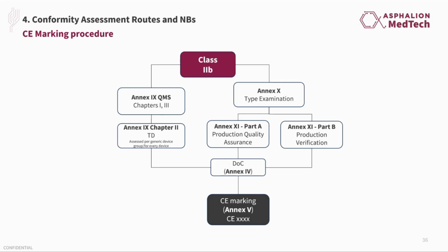A notified body verifies and certifies that a product and its technical documentation, a representative sample, and its processes comply with applicable provisions. In this case, the notified body shall carry out or request to carry out appropriate tests for the verification of compliance with the requirements, together with a review of the technical documentation. And then Annex 11, whose objective is to verify that the product conforms to the type for which the certificate was issued by the notified body following Annex 10. It presents as part A the so-called production quality assurance, which is applied by the manufacturer to ensure the maintenance of quality within its QMS, or part B, called product verification. And here there are physical and laboratory tests to verify the conformity of the devices with the type described in the EU type examination certificate according to Annex 10.